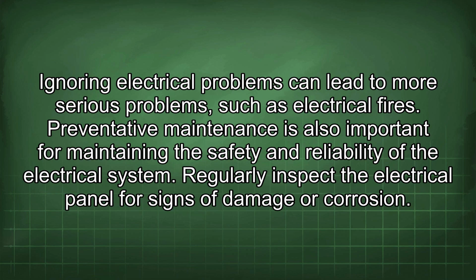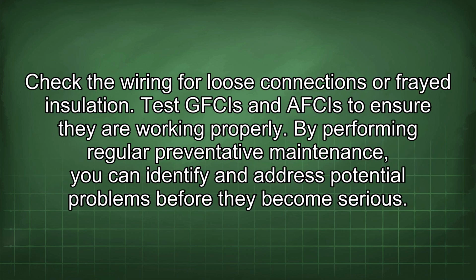Preventative maintenance is also important for maintaining the safety and reliability of the electrical system. Regularly inspect the electrical panel for signs of damage or corrosion. Check the wiring for loose connections or frayed insulation. Test GFCIs and AFCIs to ensure they are working properly. By performing regular preventative maintenance, you can identify and address potential problems before they become serious.